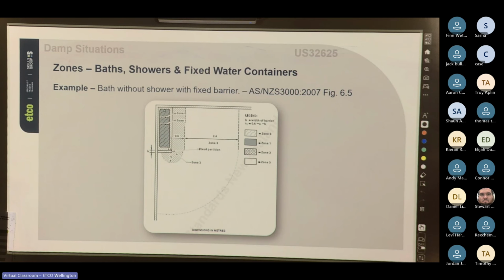So this is for a bath with a fixed barrier. For this, we're being given the top down, so zone 0 and zone 1 being the bathtub itself, zone 2 being 0.6 meters. So it's with a fixed barrier. So zone 2 extends 0.6 meters away from the wall to where the barrier is.